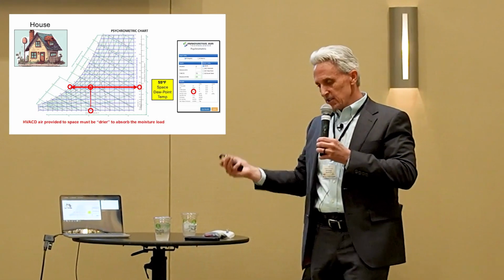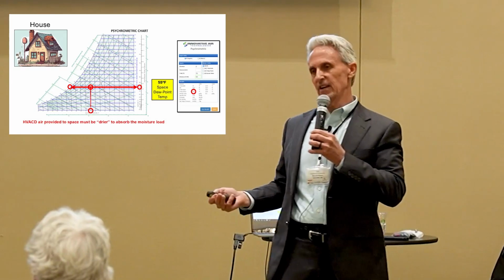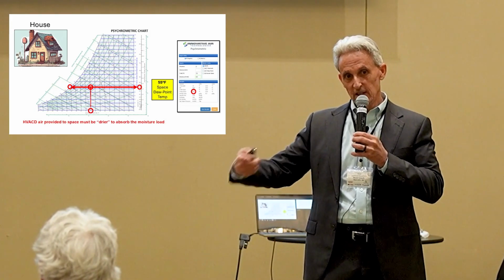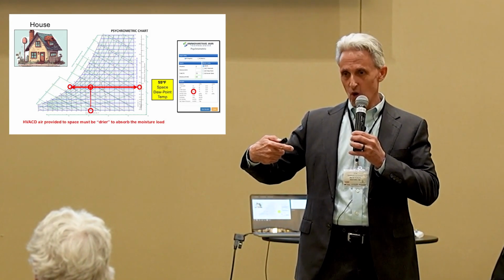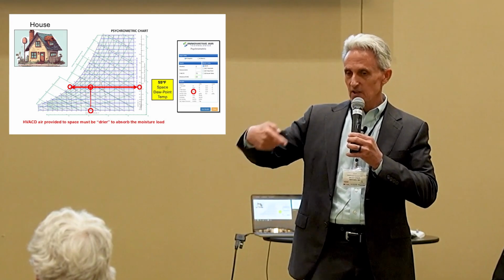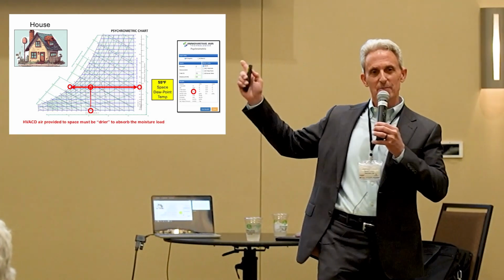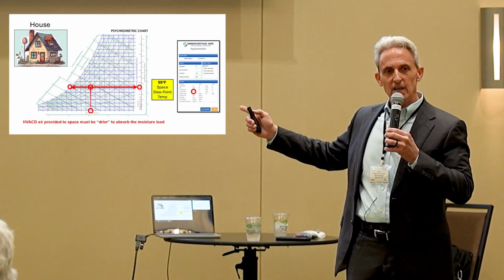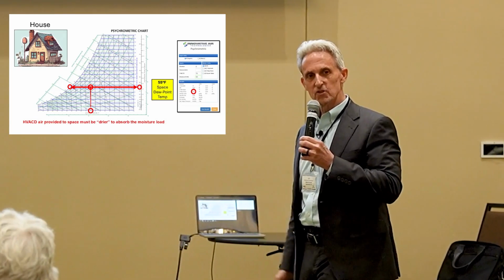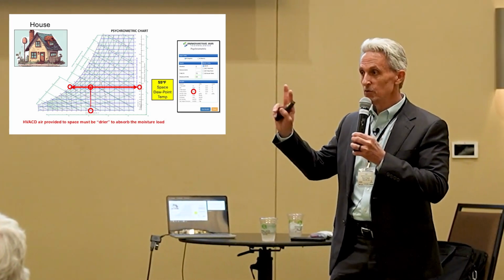All right? Look at it this way. If you're sitting in your living room in the summertime at home and you want to maintain your living room at 70 degrees Fahrenheit and it's a hot summer day outside and you turn on your air conditioner, do you blow 70 degree air out of the register to keep the space at 70 degrees? No, you can't. It's got to be a delta between the air provided and the space to absorb the air conditioning load, right? I might blow 55 degree air out of that register to maintain 70 degrees in the space. It's the same thing with moisture. The air's got to be drier than the space in order to absorb the moisture load. People forget that. Train comes off the tracks all the time. It's really important. I bring it up now because I'm going to talk about it a couple more times moving forward, okay?